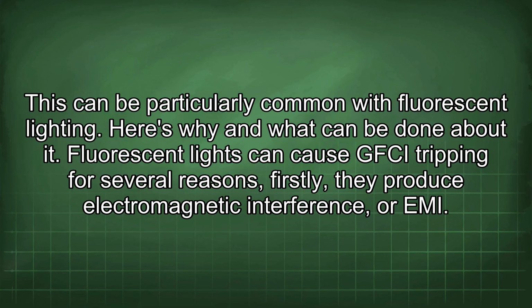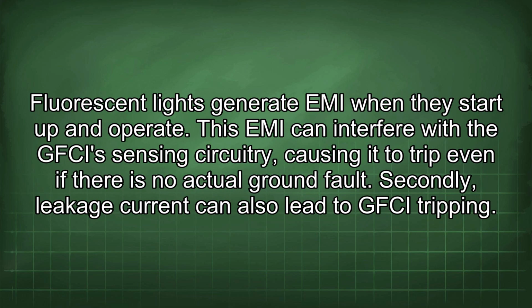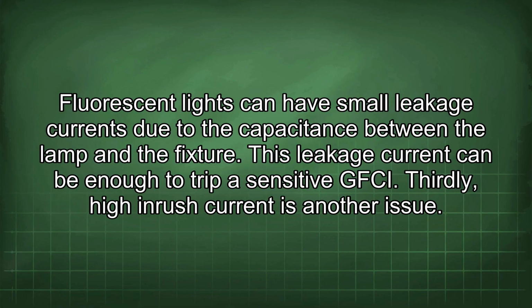Fluorescent lights can cause GFCI tripping for several reasons. Firstly, they produce electromagnetic interference, or EMI. Fluorescent lights generate EMI when they start up and operate. This EMI can interfere with the GFCI's sensing circuitry, causing it to trip even if there is no actual ground fault. Secondly, leakage current can also lead to GFCI tripping. Fluorescent lights can have small leakage currents due to the capacitance between the lamp and the fixture. This leakage current can be enough to trip a sensitive GFCI.